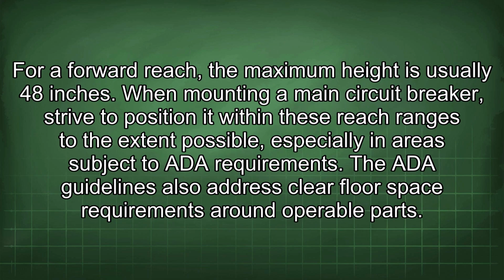For a forward reach, the maximum height is usually 48 inches. When mounting a main circuit breaker, strive to position it within these reach ranges to the extent possible, especially in areas subject to ADA requirements. The ADA guidelines also address clear floor space requirements around operable parts.